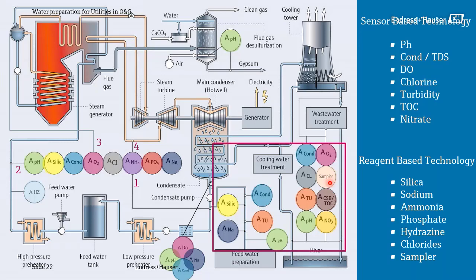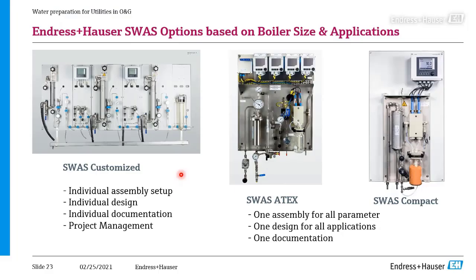So what is different with this parameter in comparison to these ones? These ones are here in the steam cycle, so we need some kind of pre-treatment in order to measure them. This is done with steam water analysis panels, because we want to detect the steam quality. In that case, we have to bring the steam back down to water, meaning we need to depressurize and cool the water in order to measure the various parameters.